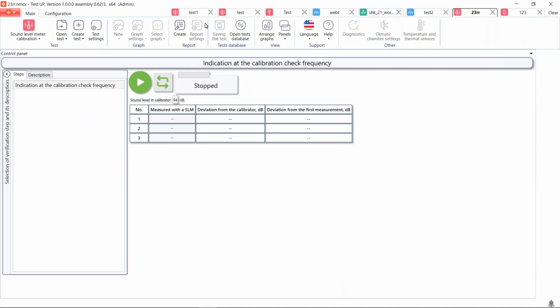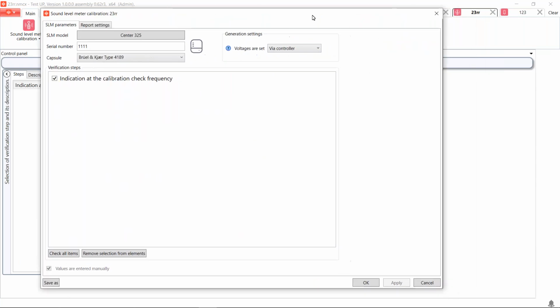So we created a list of all steps of sound level meter calibration described in its standard, IEC 61672-3, and I will show you these steps a little bit later. Just wanted to tell you about the advantage of this module. So the advantage of our module for sound level meters is that depending on the sound level meter you have, you can choose the steps you need to perform and configure the parameters in accordance with the sound level meter's passport. So now let's have a closer look at the module's capabilities while performing the calibration of the sound level meter that we have today.